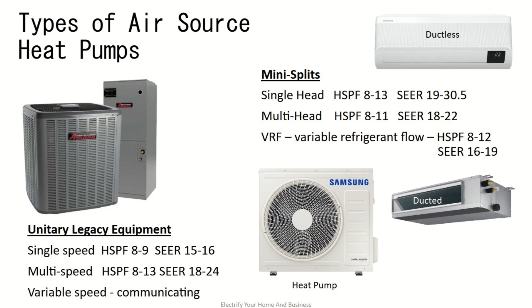The duct system, if you're doing a ducted system, is part of the entire heating and cooling system. A lot of contractors offer what we call box swaps, where they leave the duct system you already have in place and just hook the new heat pump up to it. When we test old duct systems, we find we lose about 50% of the system's capacity through this poorly constructed duct system that isn't actually designed for the equipment attached to it.